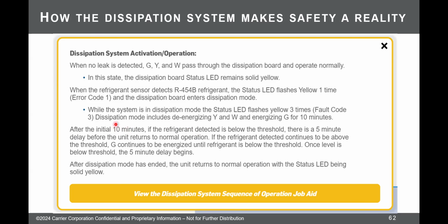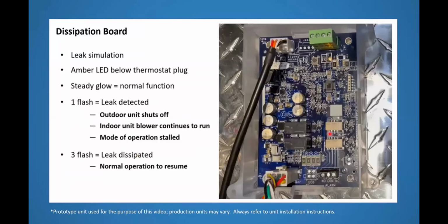It does that for 10 minutes. And assuming after 10 minutes there's no leak, which there probably won't be because you blew all the refrigerant somewhere else, then it goes ahead and runs the sequence for 5 extra bonus minutes. No heat, no cool, fan on. And after a grand total of 15 minutes, it allows heating and cooling to resume as normal. Obviously, cooling's not going to be very useful because you don't have any refrigerant, but the heating at least would go back to heating this person's house. And then if there's another leak detected later on, it all repeats again. No heat, no cool, fan on, wait 10 plus 5 minutes. If everything's good, we're ready to rip, right? So you can do that, or it will do that, I should say. And there's a circuit board that comes with this.